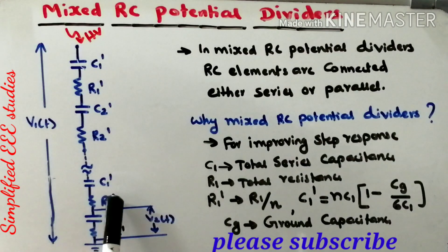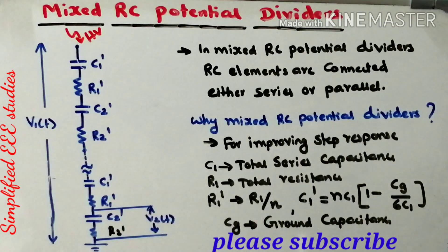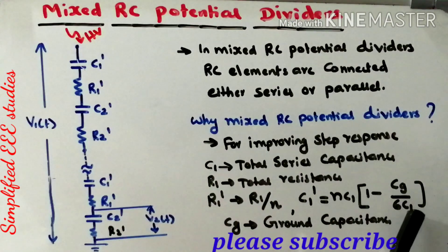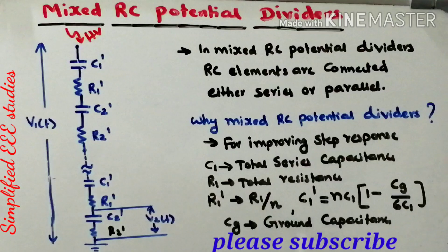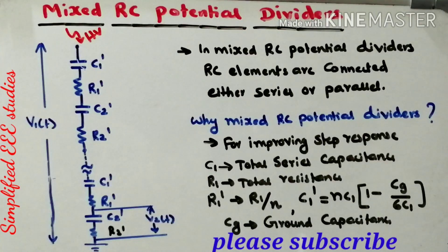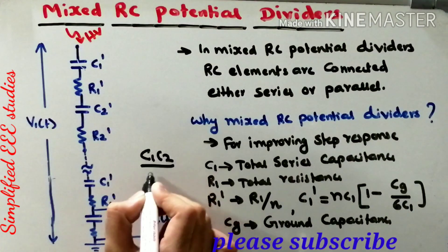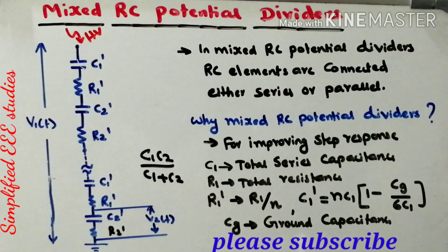By using the calculation, you are able to find the total voltage applied. R1' is nothing but R1 divided by N, where R1 is the total resistance. Similarly, C1' can be calculated using the formula NC1 multiplied by (1 minus CG divided by 6C1), where CG is the ground capacitance. For capacitors in series: C_eq equals C1·C2 divided by (C1 plus C2). For capacitors in parallel: C_eq equals C1 plus C2.